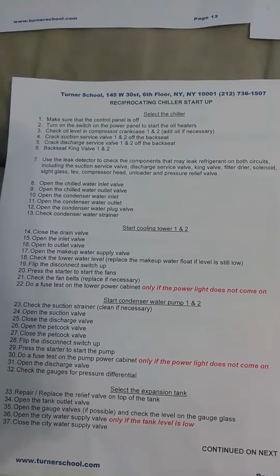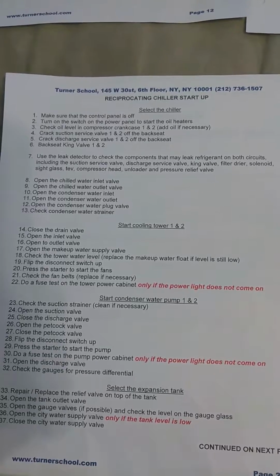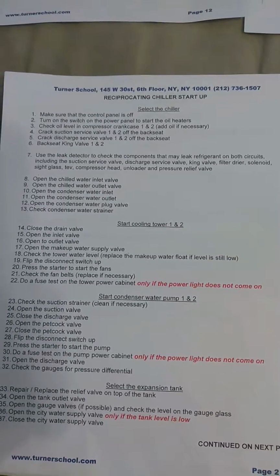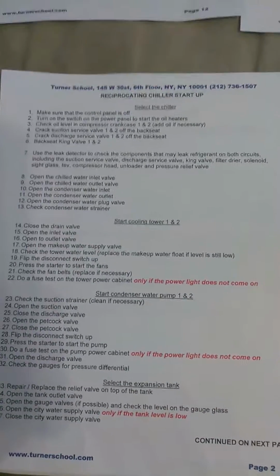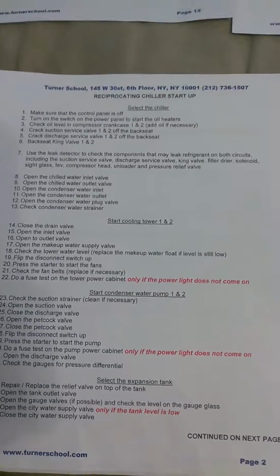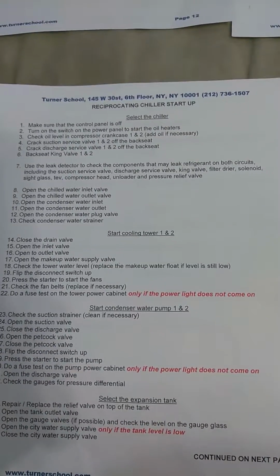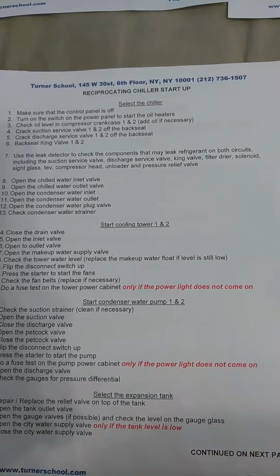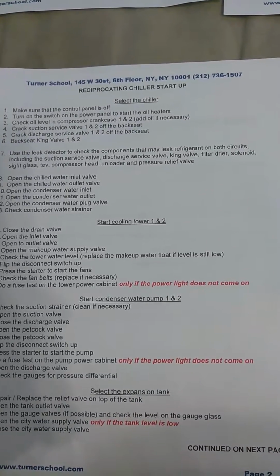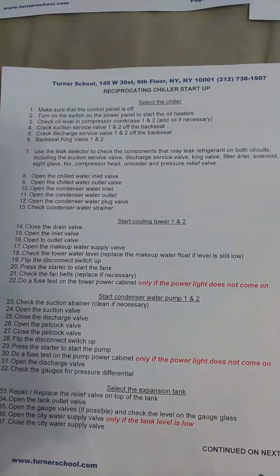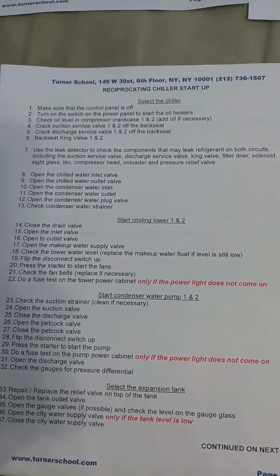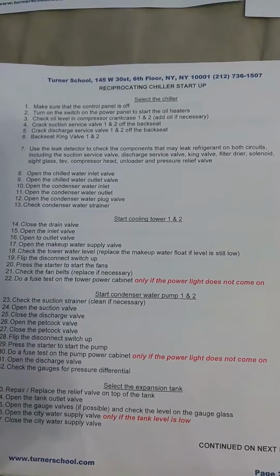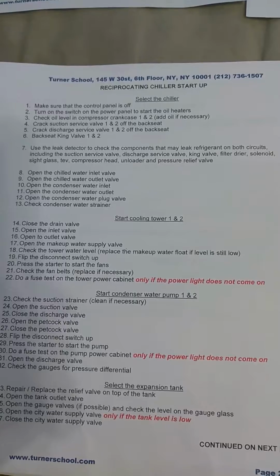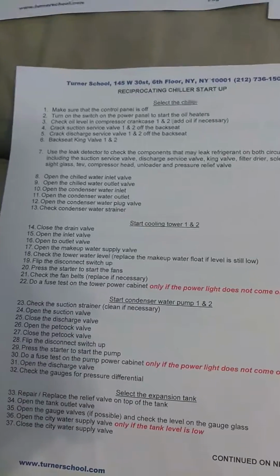Reciprocating chiller startup. Make sure the control panel is off. Turn on the switch on the power panel to start the oil heaters. Check the oil level in compressor crankcase 1 and 2. Add oil if necessary. Crack the suction service valve 1 and 2 off the back seat.